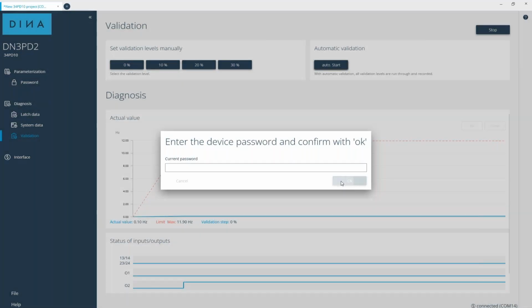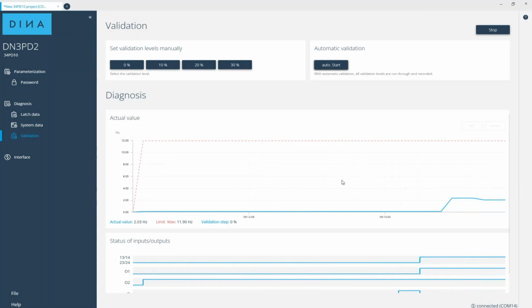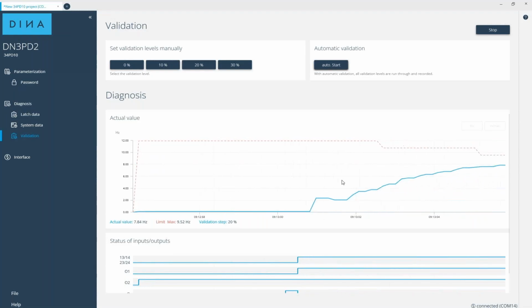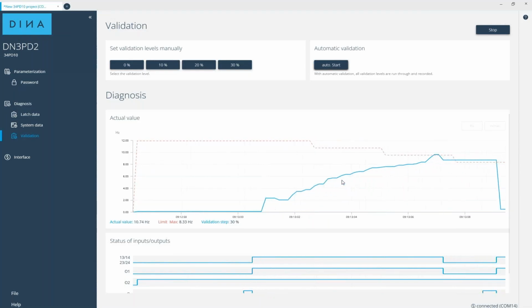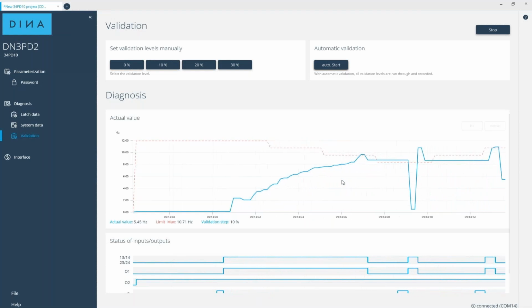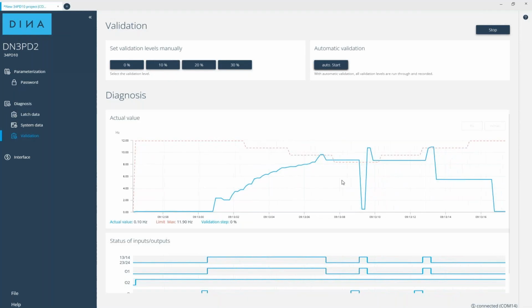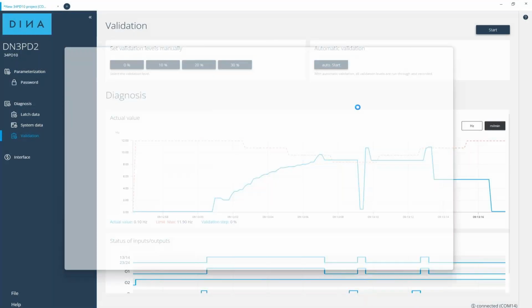And the most important part or a key function is the validation option. This process verifies the correct function of the defined safety limits, and utilizing automatic validation, the software checks the integrity against a set of predefined validation levels. Upon successful completion, the software generates the required proof of functional safety and makes it available as a PDF document. This PDF serves as the official proof of commissioning, confirming that the system is ready and complies with all safety standards. As shown, our Go Beyond software is designed to be very user-friendly and logically structured. We are confident that this ease of use guarantees that the product will be loved by its users.